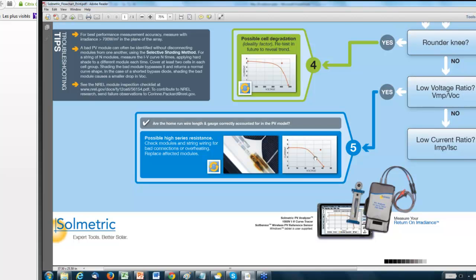Sometimes it's a bad fuse holder. For some reason it's gotten burned and it has high resistance inside of it. Sometimes it's a somewhat burned or fatigued PV connector in the interconnection circuitries. Sometimes it's in the modules within a cell. Sometimes it's visible as a burn mark. Sometimes you can see it with your IR camera. Sometimes it's within the wiring within the module.